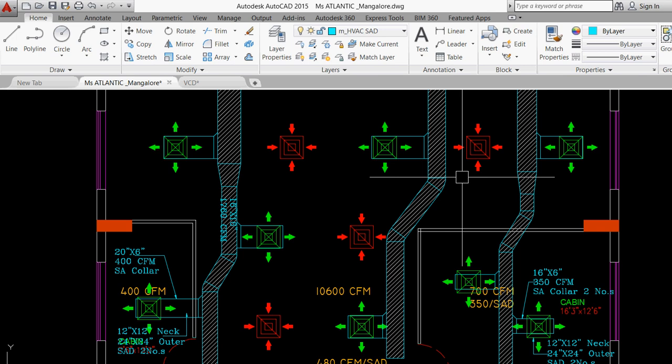So shall I design it for 500 fpm? If I design it for 500 fpm, this is 700 cfm. So if this is 700 cfm, and the duct velocity I'll consider as 500 or 450 fpm, and the duct height, say for example 16 inches. Supply, written also around, I can make it with 16 inches, assuming it is not intersecting with your supply again.